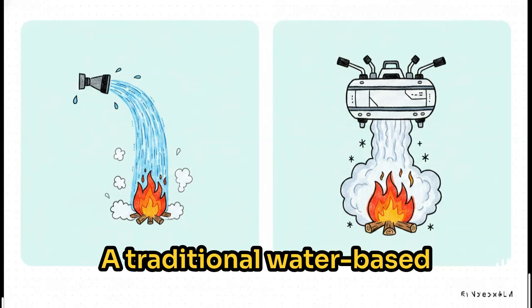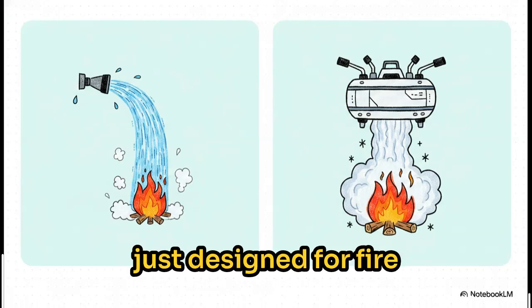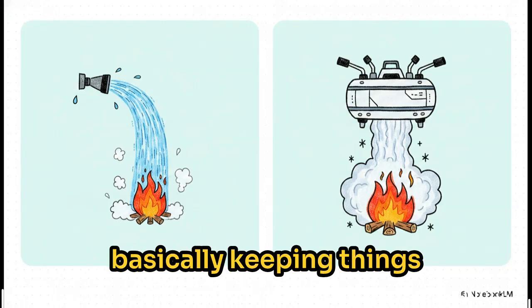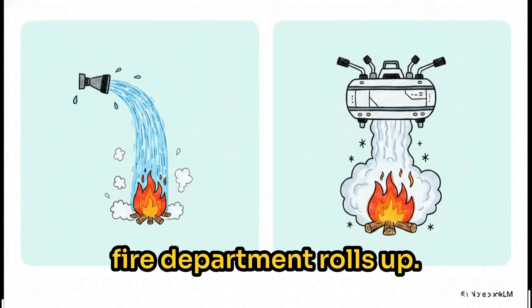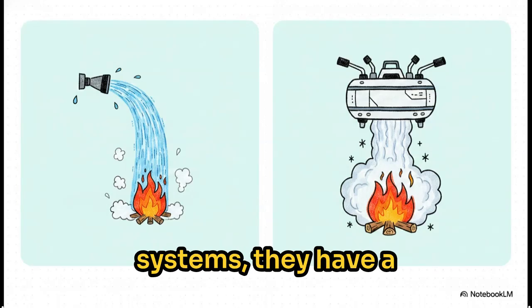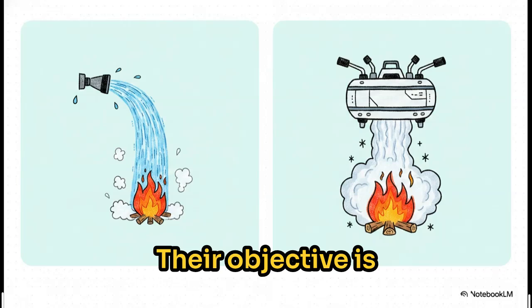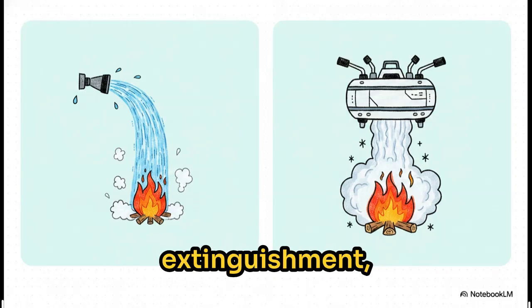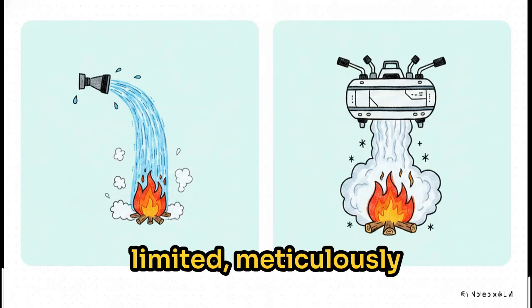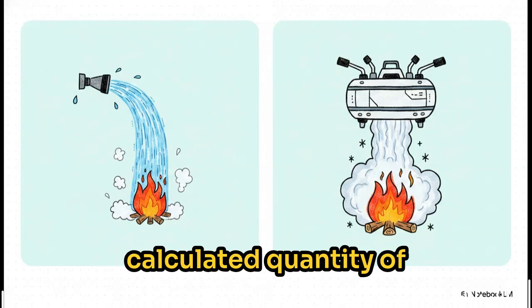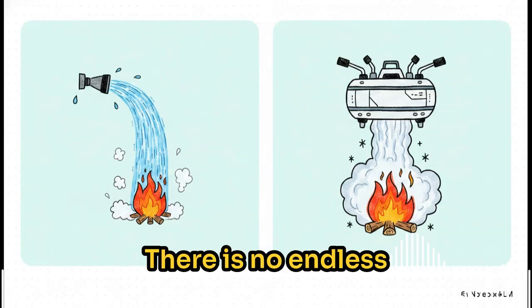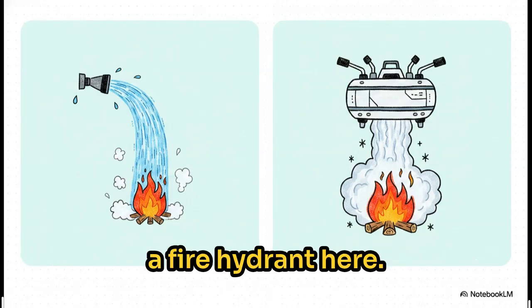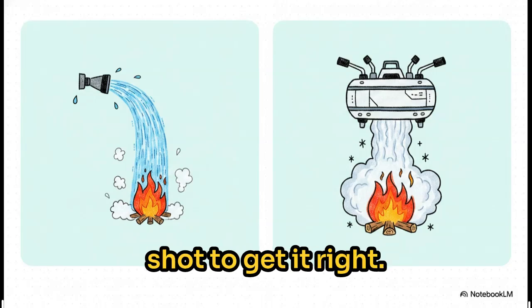A traditional water-based system is generally just designed for fire control or containment, basically keeping things manageable until the fire department rolls up. But special agent systems, they have a much heavier burden. Their objective is complete and total extinguishment, and they have to pull it off with a highly limited, meticulously calculated quantity of extinguishing agent. There is no endless supply of water from a fire hydrant here. They get exactly one shot to get it right.